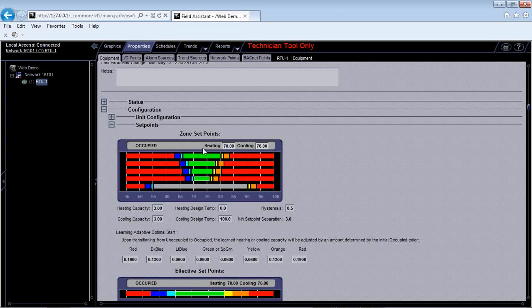So these different bars actually represent different levels, right? Right now I'm clicked on this fourth bar down, which is my occupied level. If I go one below it with this gray bar, this is my unoccupied set point level. So you can see my unoccupied is 55 and 90. You can make these changes like we did on the graphic originally, but this just allows you to do it a little quicker, and you can actually make changes to the different color ranges. So right now I have a color range in this yellow where I have 76 to 77. I can actually broaden that and make it 76 to 80 that I want to show yellow, and then you can see it slides over for all of them here.